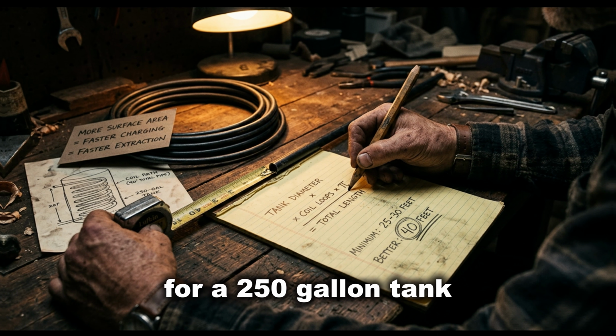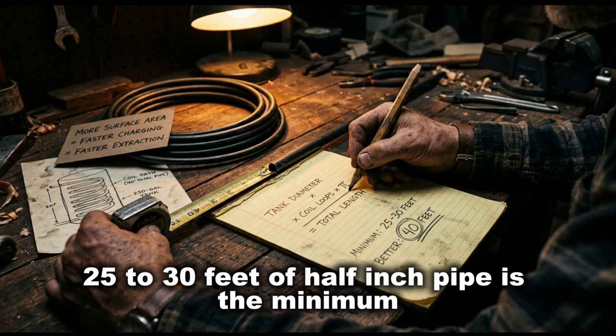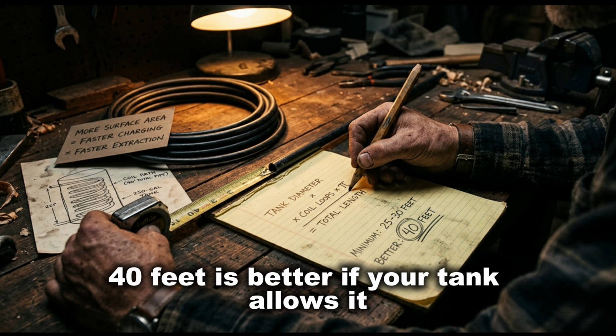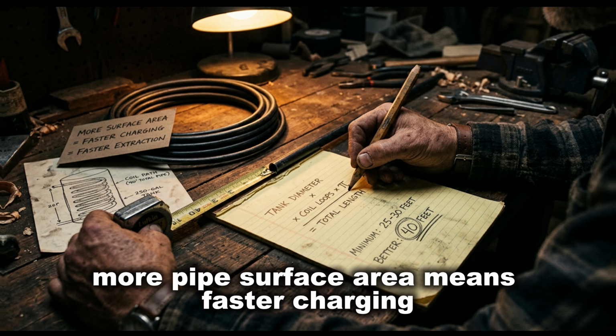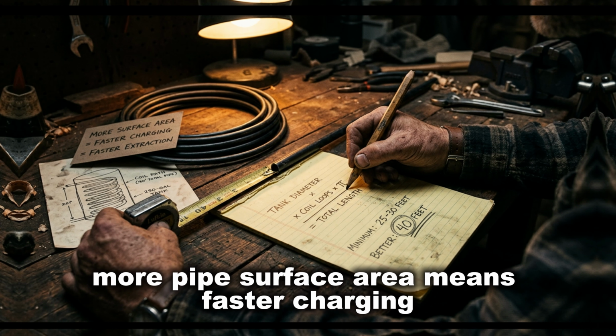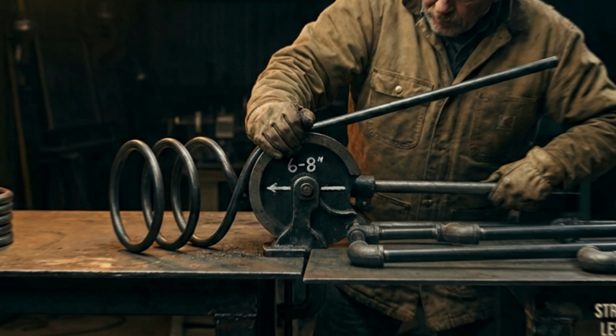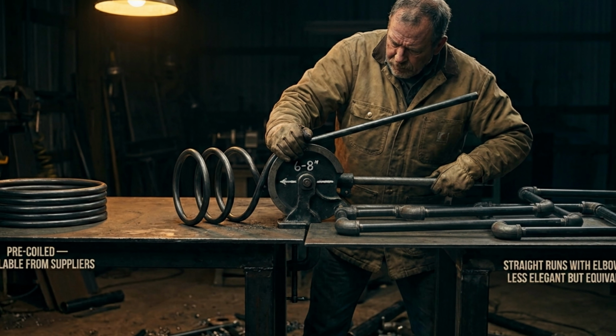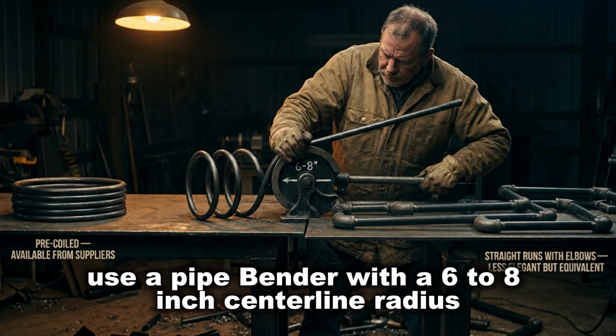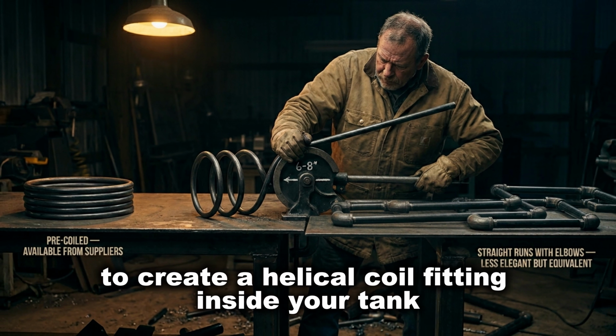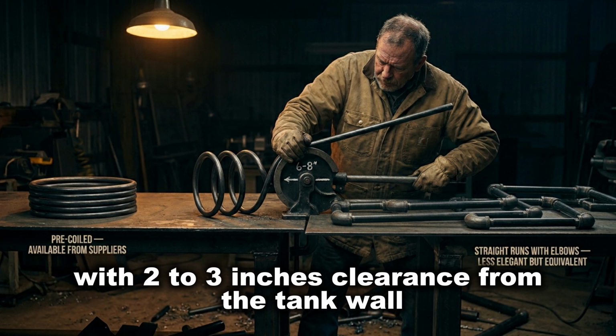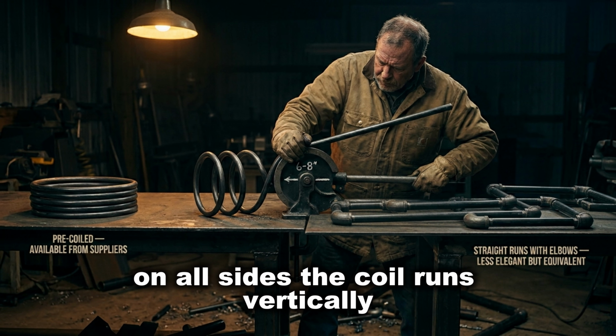For a 250-gallon tank, 25 to 30 feet of half-inch pipe is the minimum. 40 feet is better if your tank allows it. More pipe surface area means faster charging and faster heat extraction. Step 2. Bend your coil. Use a pipe bender with a 6 to 8 inch centerline radius to create a helical coil fitting inside your tank with 2 to 3 inches clearance from the tank wall on all sides.